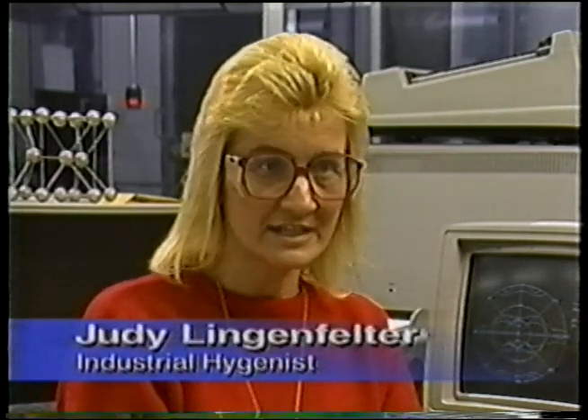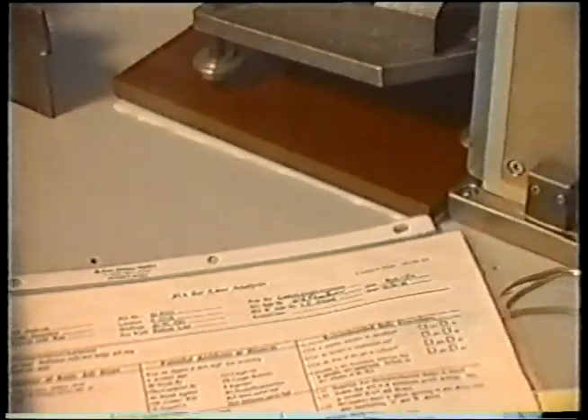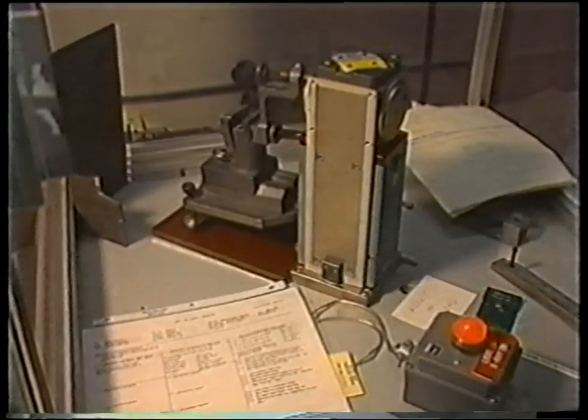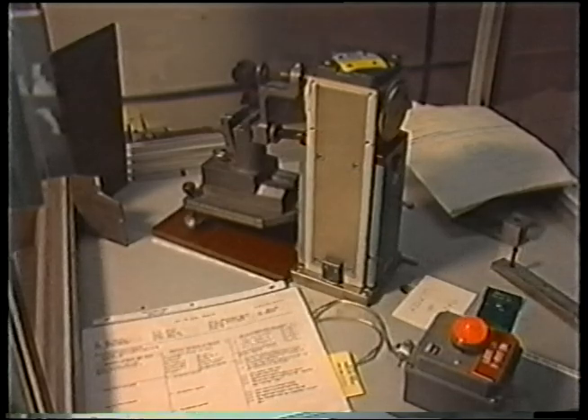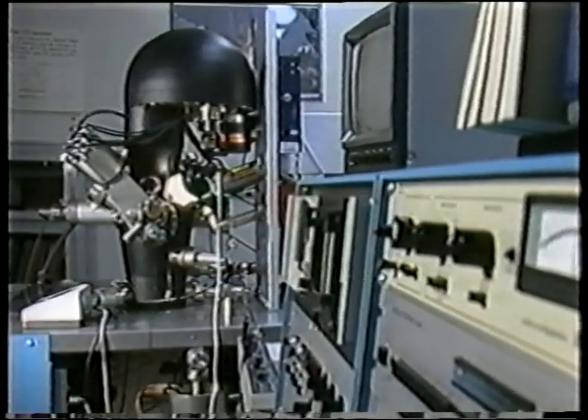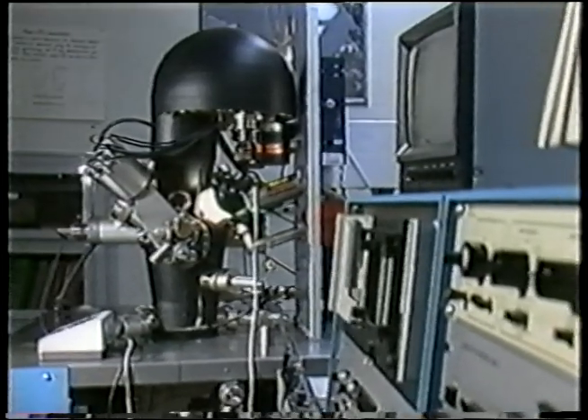It's important to request a project health and safety review and a formal survey after a modification has been done to X-ray producing equipment. This will ensure that there's no X-ray leakage out into the area where people are working and could be exposed. We have JSAs, which are formal safety written procedures that's used here at the Tech Center. It details how the X-ray producing equipment should be used and what the safeguards are that are in place. We must do everything we can to minimize the risks associated with X-ray producing equipment.